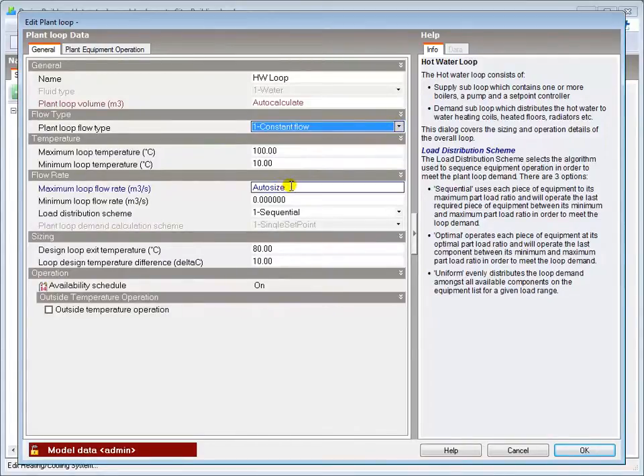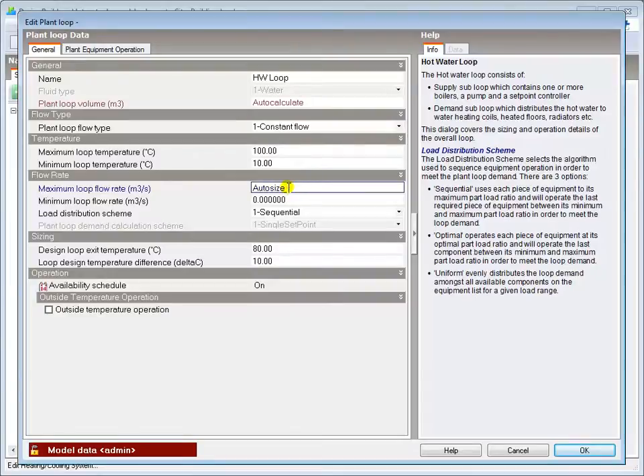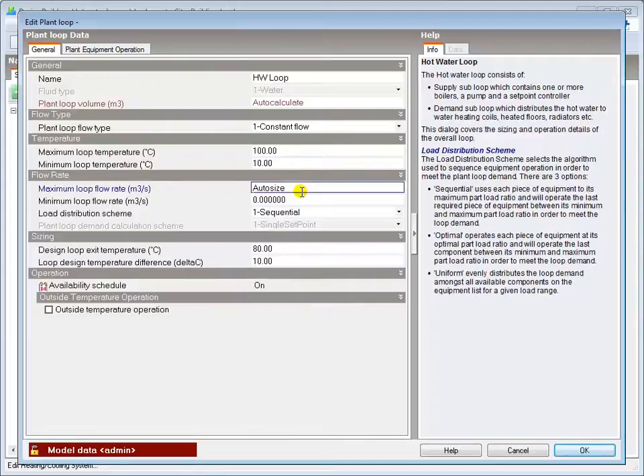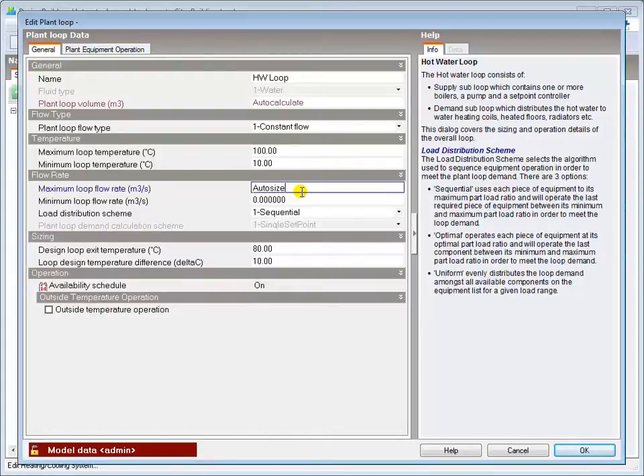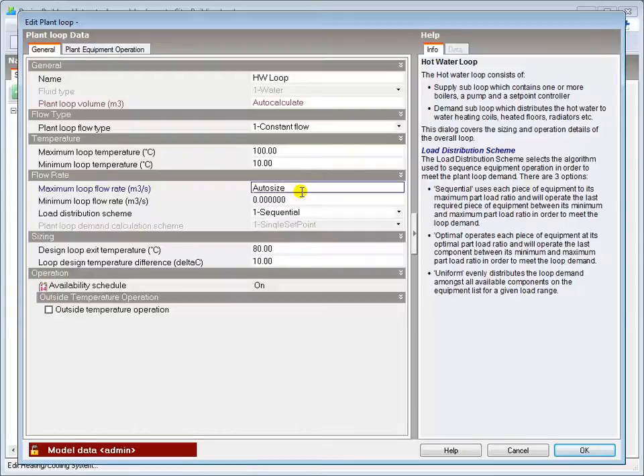You'll see this blue auto-size input on many of the edit dialogs. If the auto-size option is used, that element of the system will be automatically sized by EnergyPlus in the HVAC auto-sizing simulation and the calculated values used as inputs to the subsequent EnergyPlus simulation. You can enter your own value if you have appropriate data.